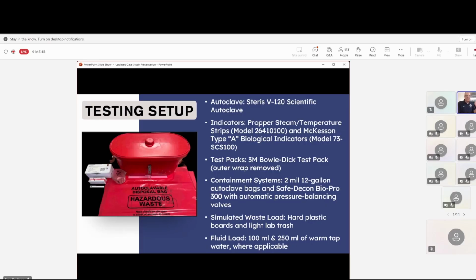And then I use the McKesson Type A biologicals, the Model 73, which has had the highest amount of spore counts in it. Then I use a test pack, a 3M Bowie Dick test pack. And what I did is I used this as a challenge pack. I'll show you that in a picture here in a minute. My containment systems are going to be the 2 mil 12-gallon autoclavable bags.